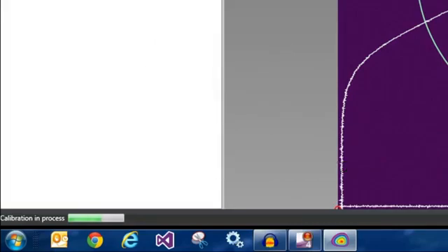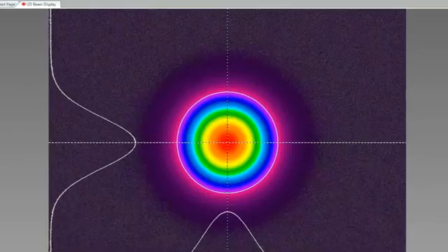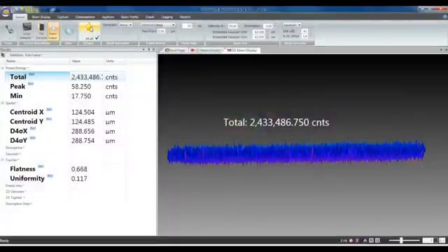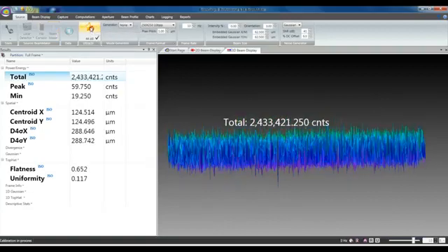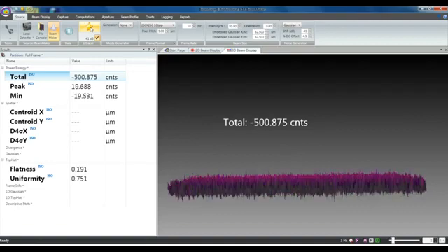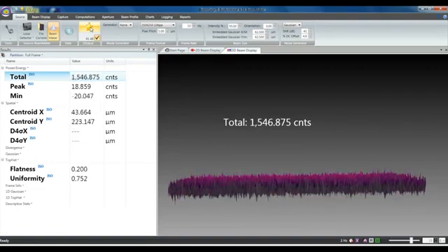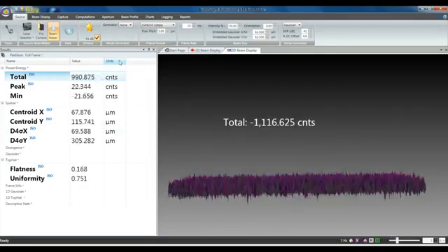The baseline, or zero, of a camera will drift with time and temperature changes and include random noise. UltraCal is the only beam profiler algorithm that sets the baseline to zero and in the center of the noise. Commonly used simple approaches use less sophisticated algorithms that perform a baseline subtraction but truncate the noise below the zero of the baseline. This leaves only a positive component, which adds a net value to all beam measurements.